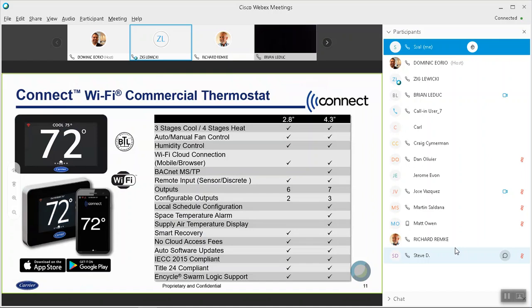Whether you're standing in front of it or using an app, you can do scheduling, fully compatible with the local application. We added things like space temperature alarms, and supply temperature display was also added. And again, it's IECC 2015 compliant, and Title 24 compliant for folks in California. It's a Connect stat, so there are other functions or applications that can log into the stats, things like Insight and Swarm Logic, which there's a lot of information on in our HVAC partners area for those that are interested.